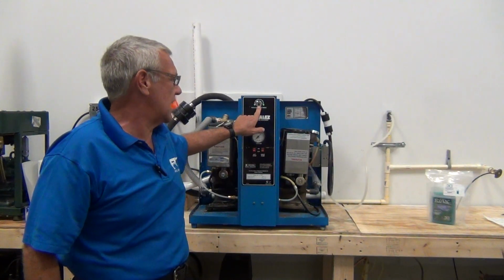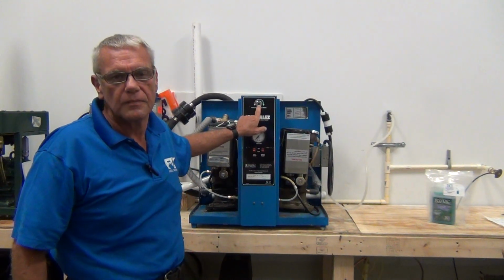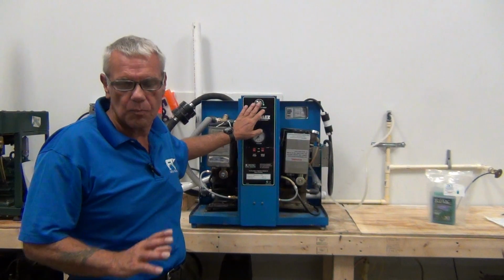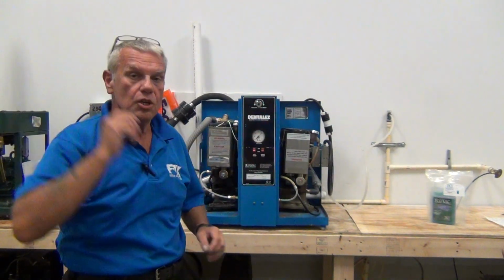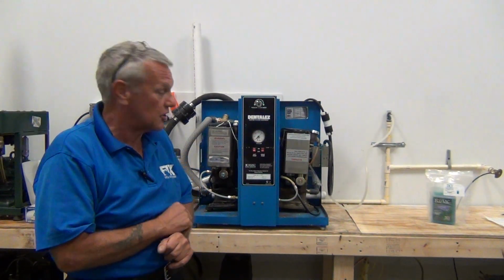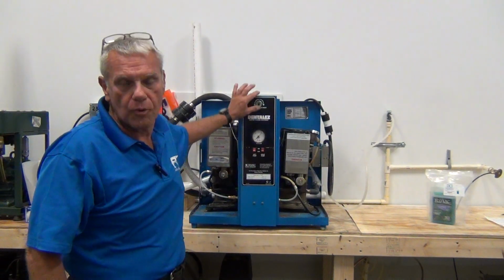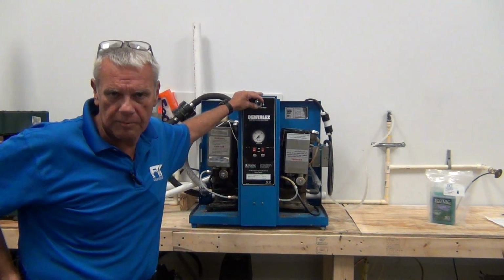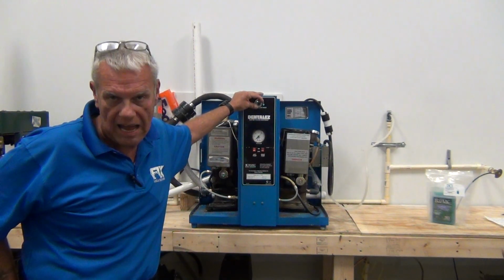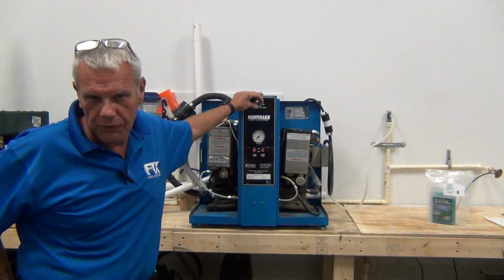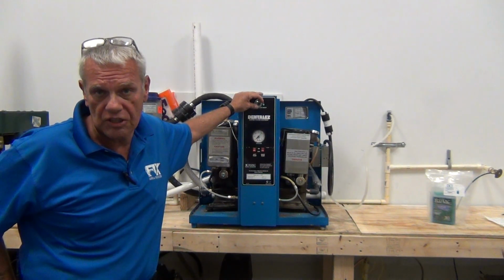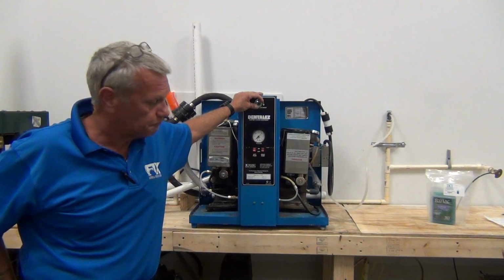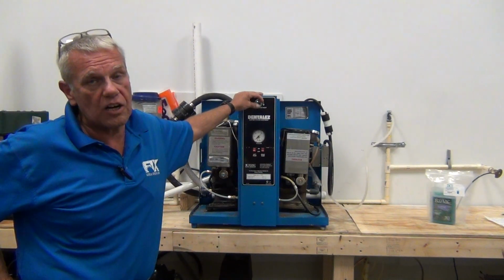The screw is missing out of the vacuum relief valve. There's no way to adjust the vacuum pressure on this machine should we need to adjust. So right off we have a suggestion to the doctor to replace the vacuum relief valve. About a $300 to $400 part. Good sale. Next we're going to check our water flow.